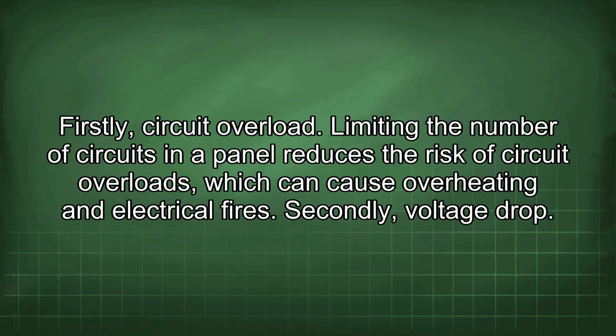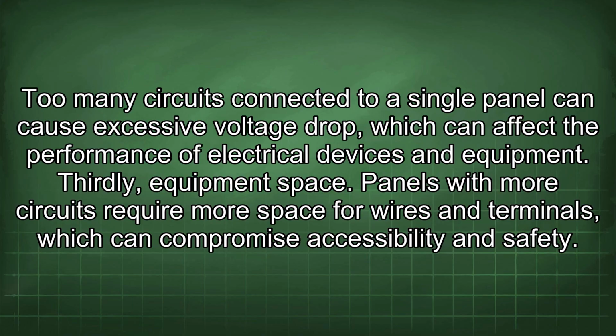Firstly, circuit overload. Limiting the number of circuits in a panel reduces the risk of circuit overloads, which can cause overheating and electrical fires. Secondly, voltage drop. Too many circuits connected to a single panel can cause excessive voltage drop, which can affect the performance of electrical devices and equipment. Thirdly, equipment space. Panels with more circuits require more space for wires and terminals, which can compromise accessibility and safety.